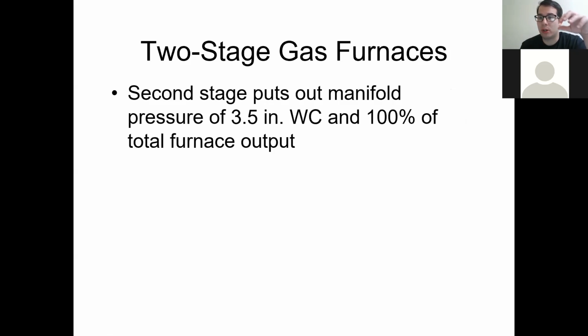The thing to understand when you're troubleshooting and maintaining these is to check whether, if it's a two-stage gas furnace, it is in the first stage or the second stage. If you're checking only first stage gas pressure, an easy thing is to hit the thermostat up 1 degree, just 1 degree. It should kick on that first stage heating, and that would be the only amount of heat allowed through. It depends on the manufacturer. If you're checking for second stage pressure, just crank up the thermostat 2 or 3 degrees at least, and it's going to go full speed, full gas pressure, through the system.